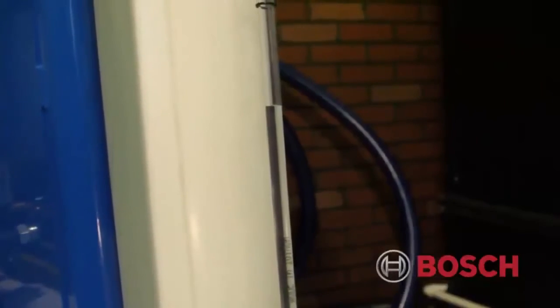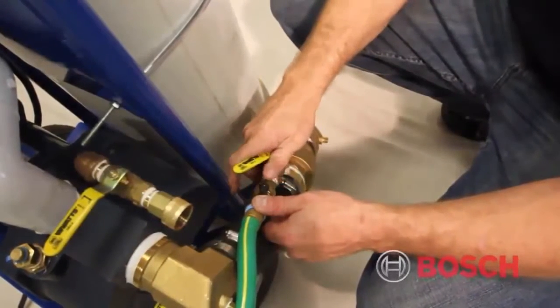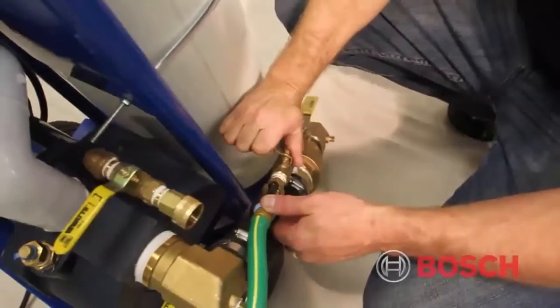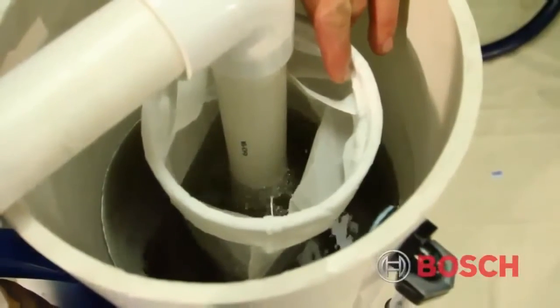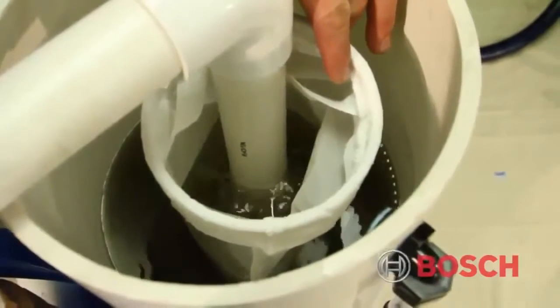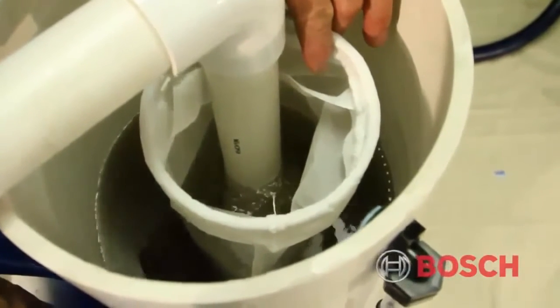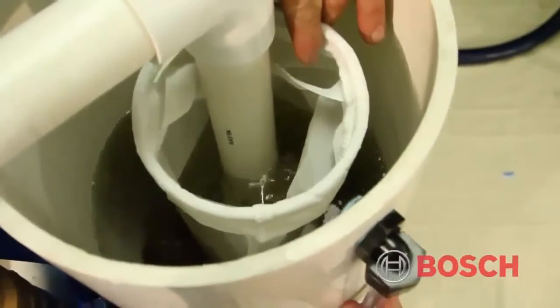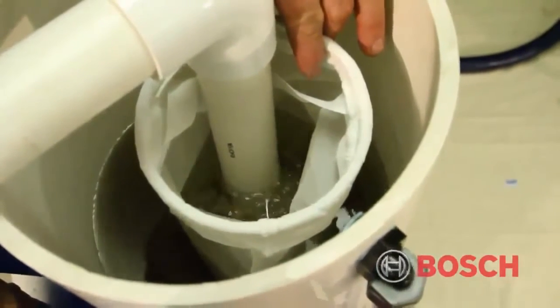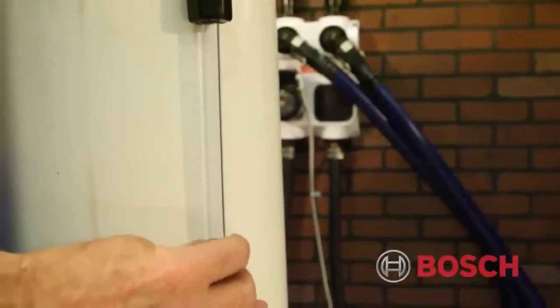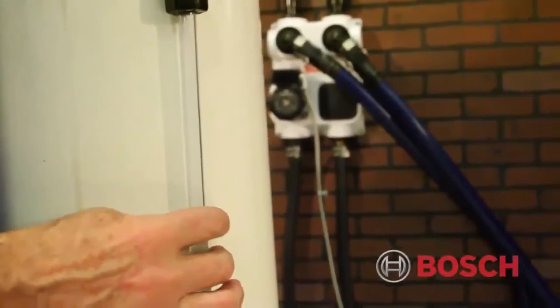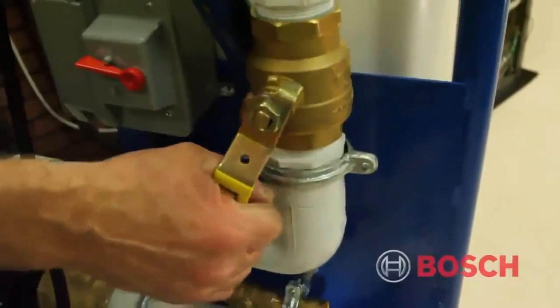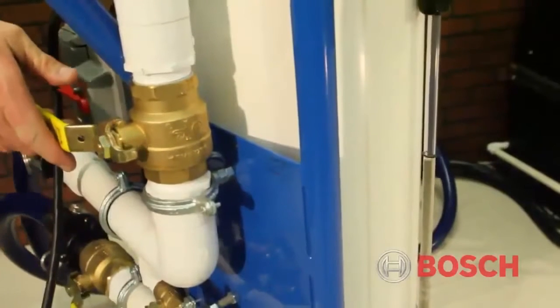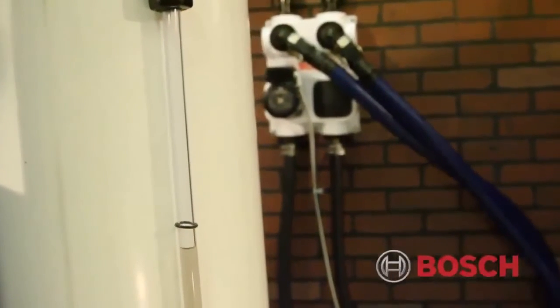Once the reservoir water level is reasonably stable or begins to increase, turn the makeup water down or off as conditions dictate. Observe the discharged water as it re-enters the reservoir. Watch for air bubbles being discharged into the reservoir. To verify possible air pockets in the loop field, a deadhead process is necessary. But before we do this, mark the level of the water by adjusting the black ring on the reservoir sight glass tube. Start the deadhead process by closing the 1.5-inch flush cart return valve and monitoring the fluid level.